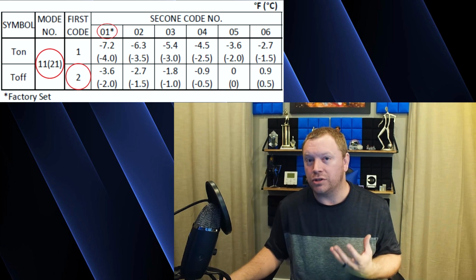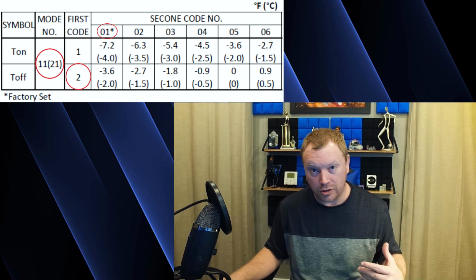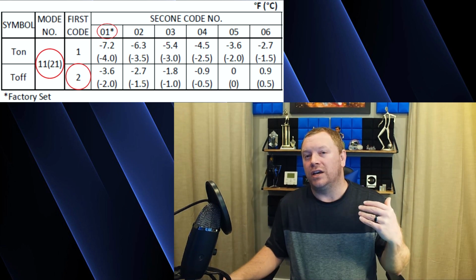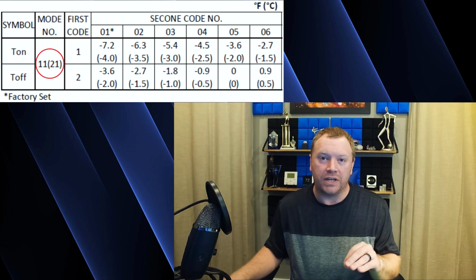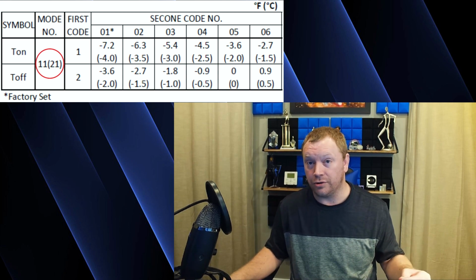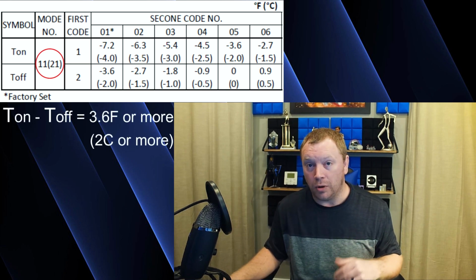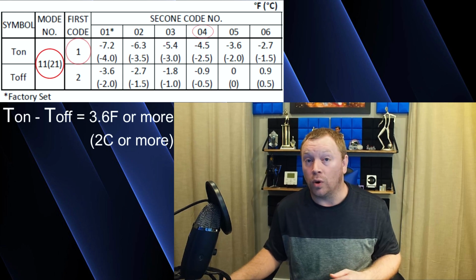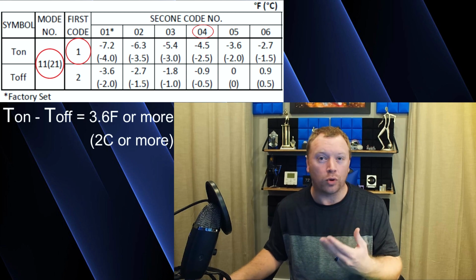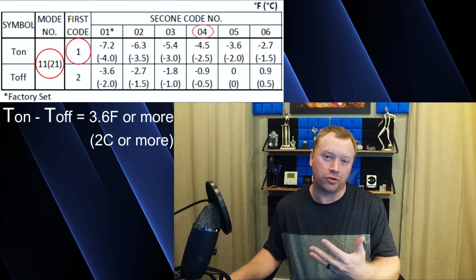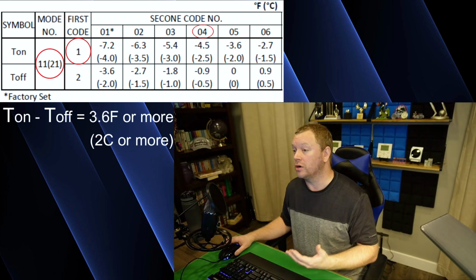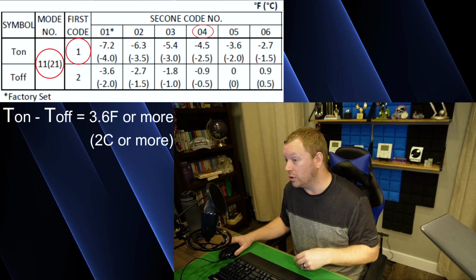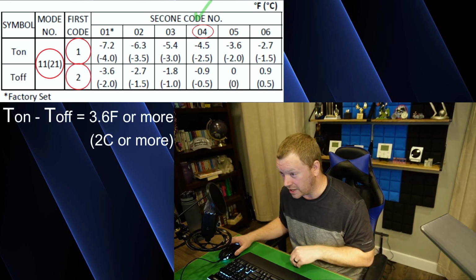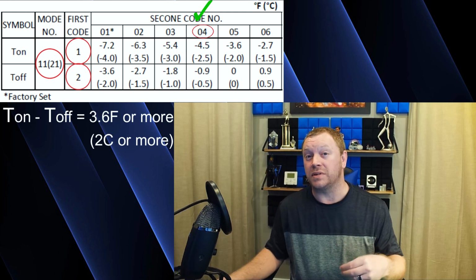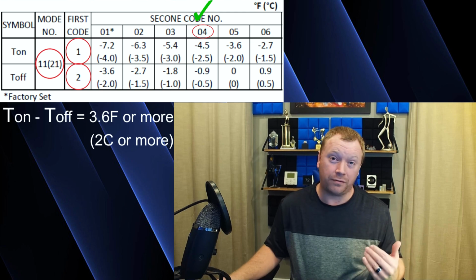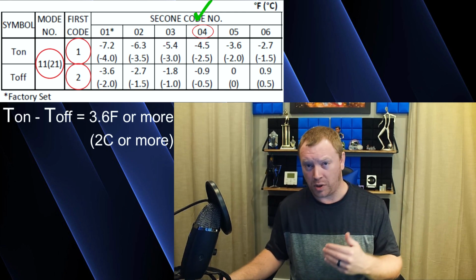Again, to reiterate, that is 7.2 degrees below the set point is where the room temperature will kick on the strip heat. When it gets to 3.6 degrees below the set point, it will then turn off the strip heat. The only rule here is you have to have the strip heat on for at least 3.6 degrees of recovery. So if you wanted to change mode 21 setting 1 to, let's say, option 4, 1-04, that is a 4.5 degree droop or drop from set point. So if my set point is 70, the room temperature is allowed to fall 4.5 degrees Fahrenheit before it turns on the strip heat. Then I would have to make sure I set mode 21 setting number 2 also to option 4, 2-04, because my on minus my off temperatures have to be at least 3.6 degrees. 4.5 drop from set point is on, 0.9 degrees below set point is my off temperature.